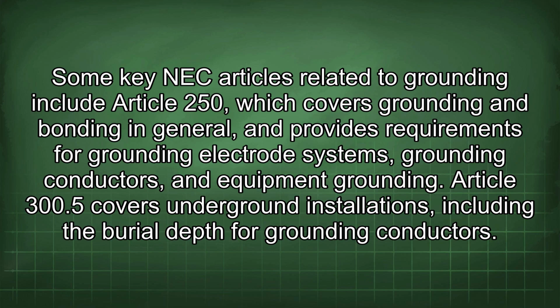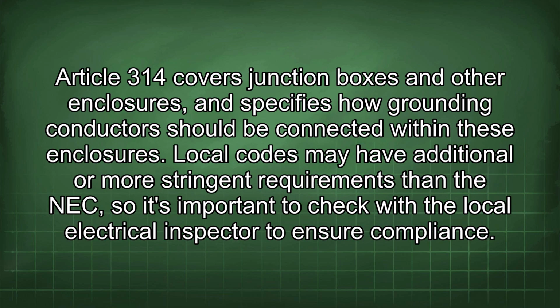Article 300.5 covers underground installations, including the burial depth for grounding conductors. Article 314 covers junction boxes and other enclosures, and specifies how grounding conductors should be connected within these enclosures. Local codes may have additional or more stringent requirements than the NEC, so it's important to check with the local electrical inspector to ensure compliance.